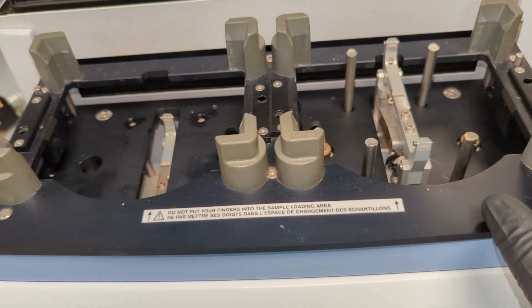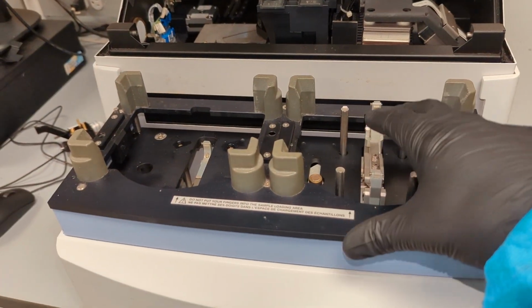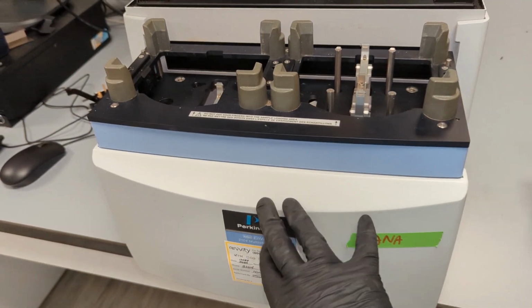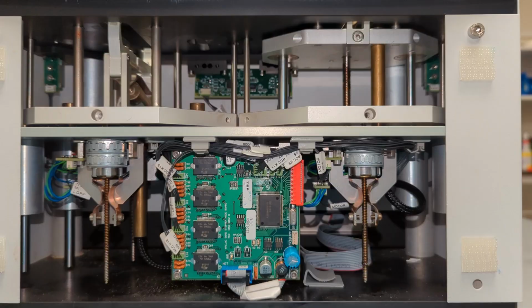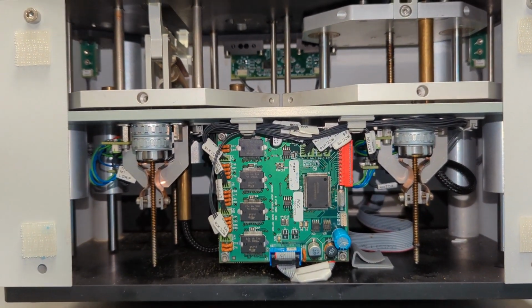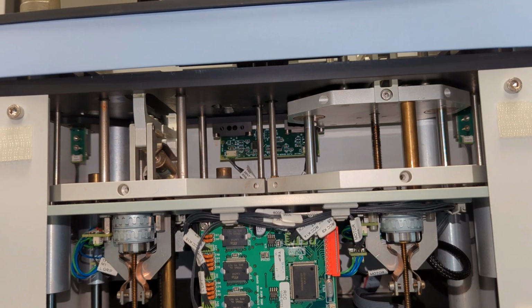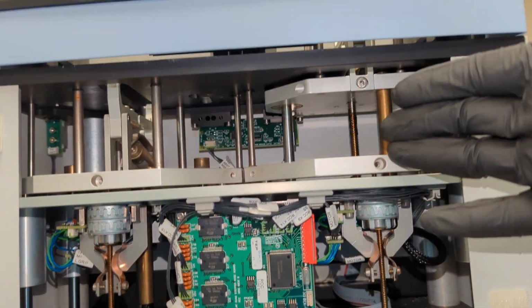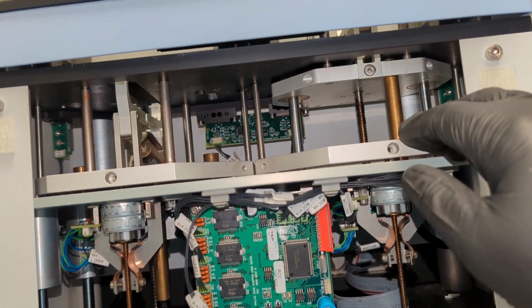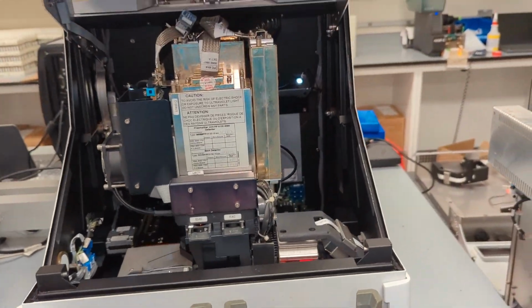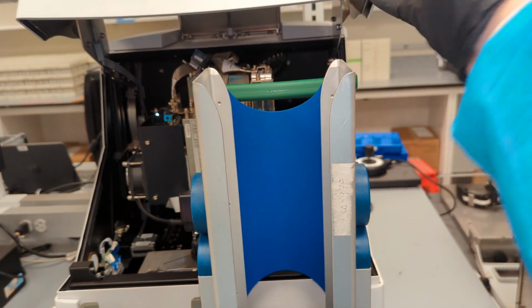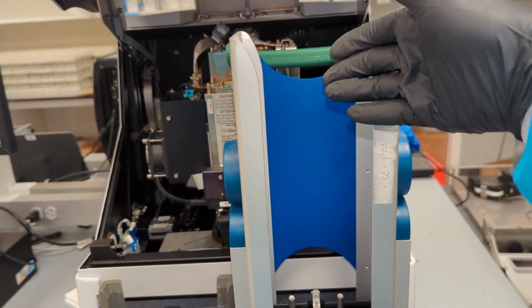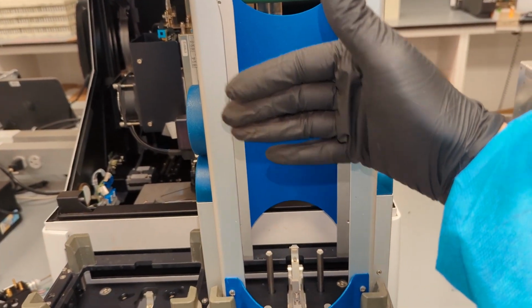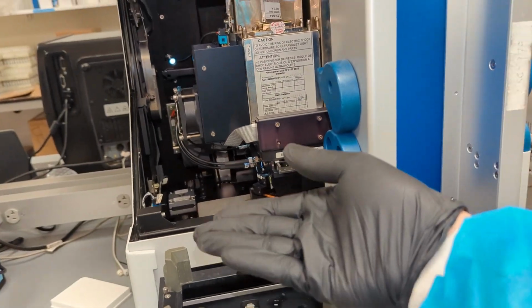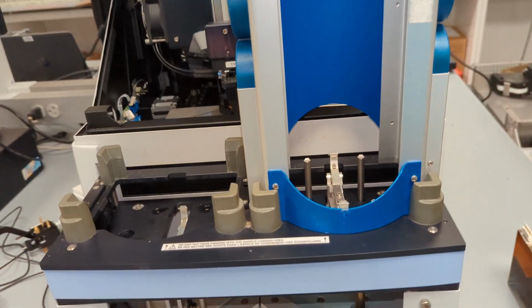Here again, you've got the plate stacker set up, and we can pop this panel off so we can actually see what's going on here. Alright, so this is the stacker assembly, and you can see here you've got some motion components. A lot of Acme screws are being used, and the only function that this thing does is you're going to take a stack of plates. You're going to stack your plates up using this guide rail assembly, and all this is doing is the plates are going to start getting lower and lower in this stack as they're fed into the instrument, and then they're going to get piled up into this stack. That's all this assembly does.